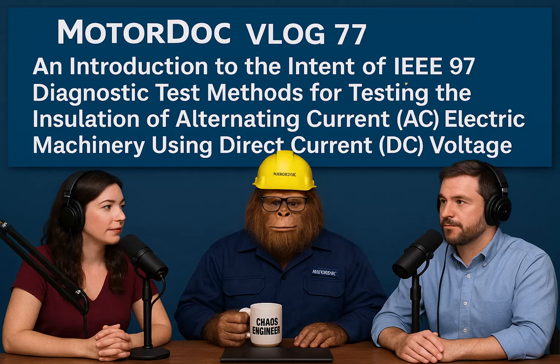You need consistent testing procedures. You need to control for those environmental factors as much as possible, or at least document them. You need to carefully account for, or preferably isolate, other connected circuit components. And maybe most importantly, history. Building that history of test data over time for your specific machines, that is absolutely non-negotiable for effective trending and diagnosis. Without that history and that consistency in how you test, you're really missing out on the full diagnostic potential these methods offer.